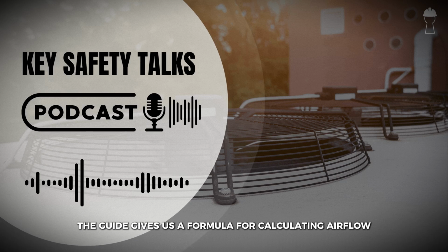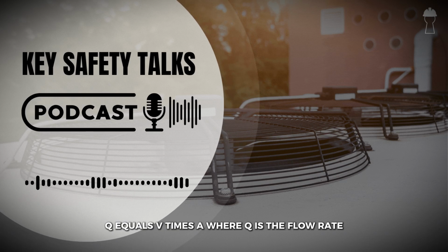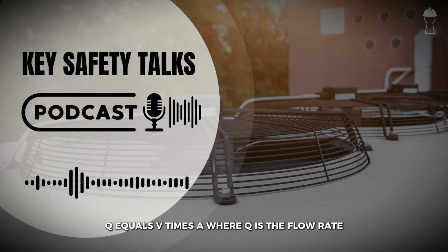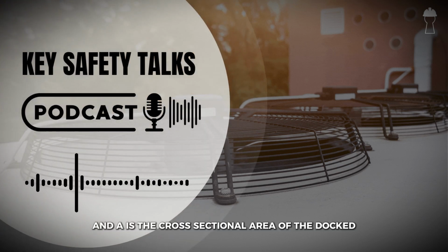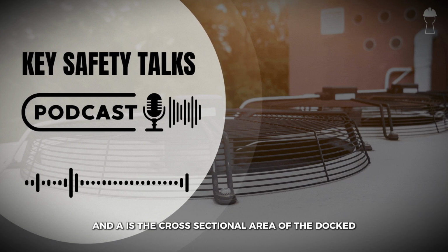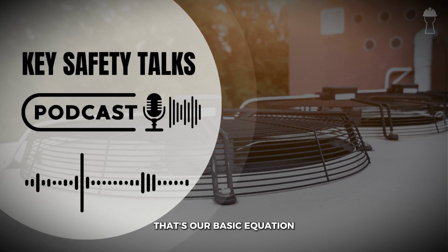So the guide gives us a formula for calculating airflow. Q equals V times A, where Q is the flow rate, V is the velocity of the air, and A is the cross-sectional area of the duct or opening. Right. That's our basic equation.